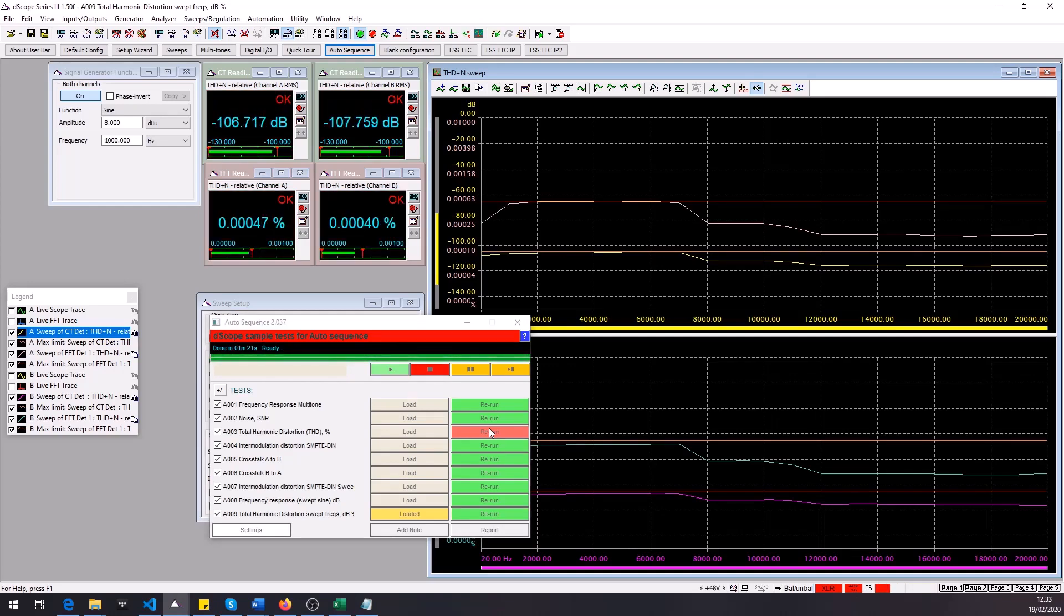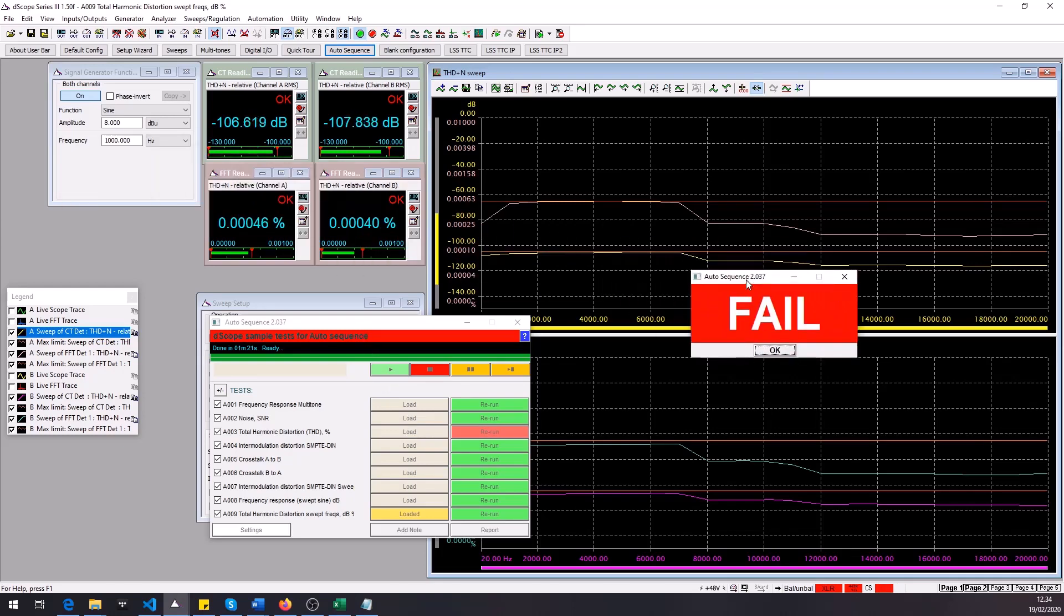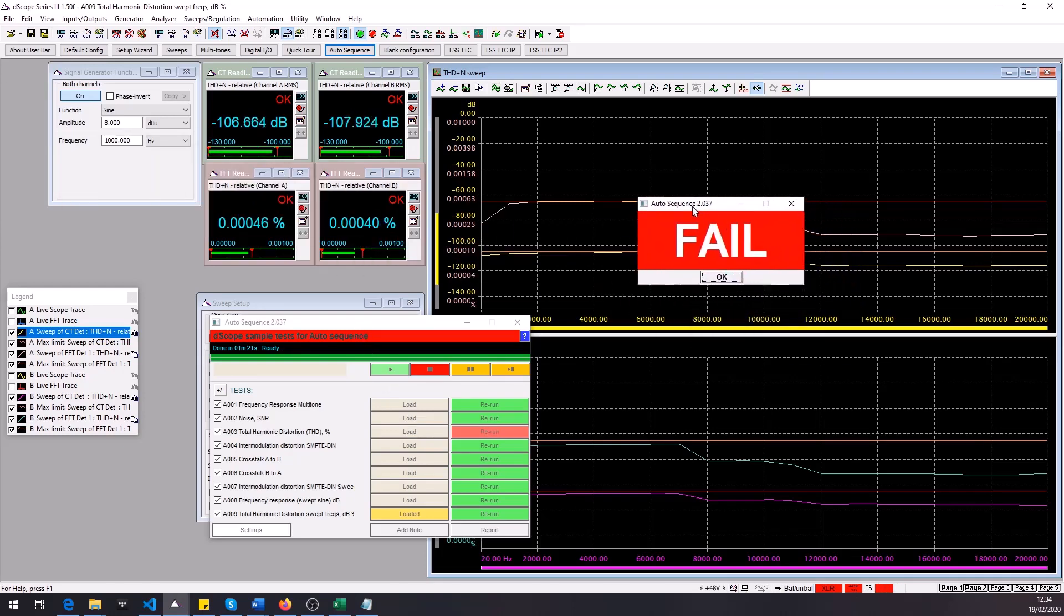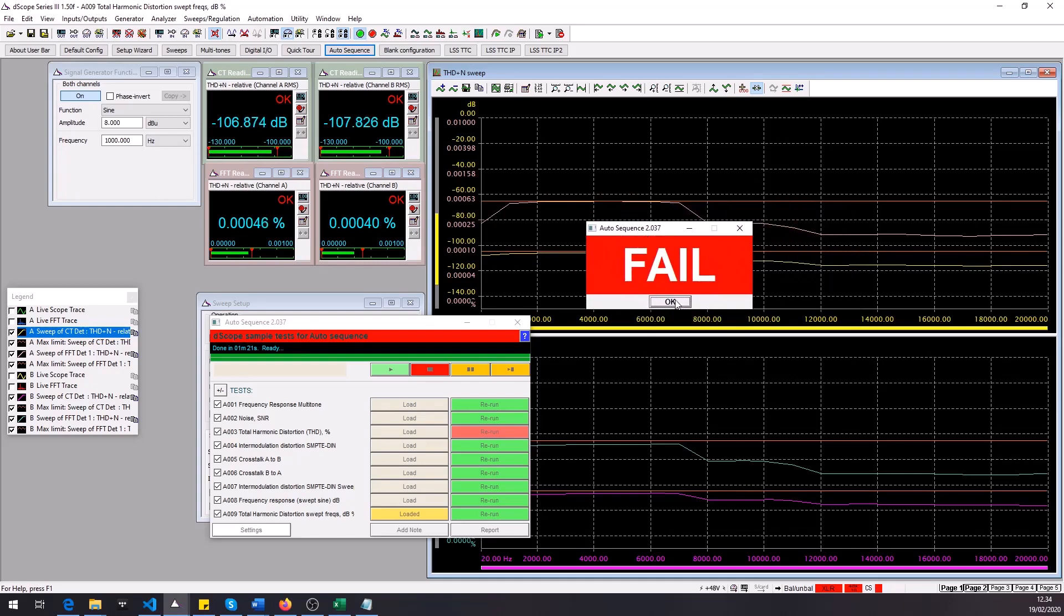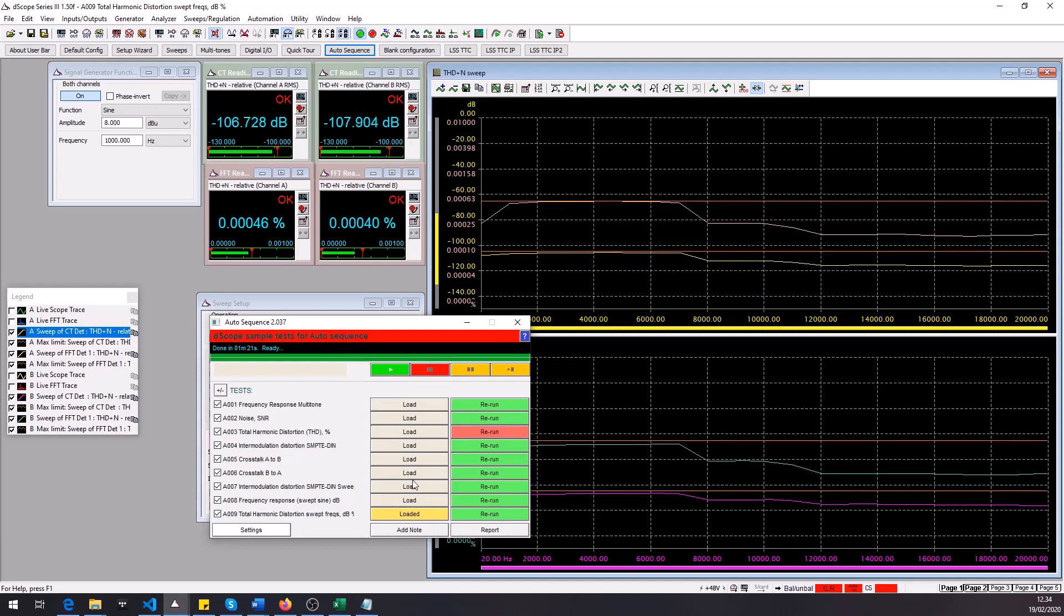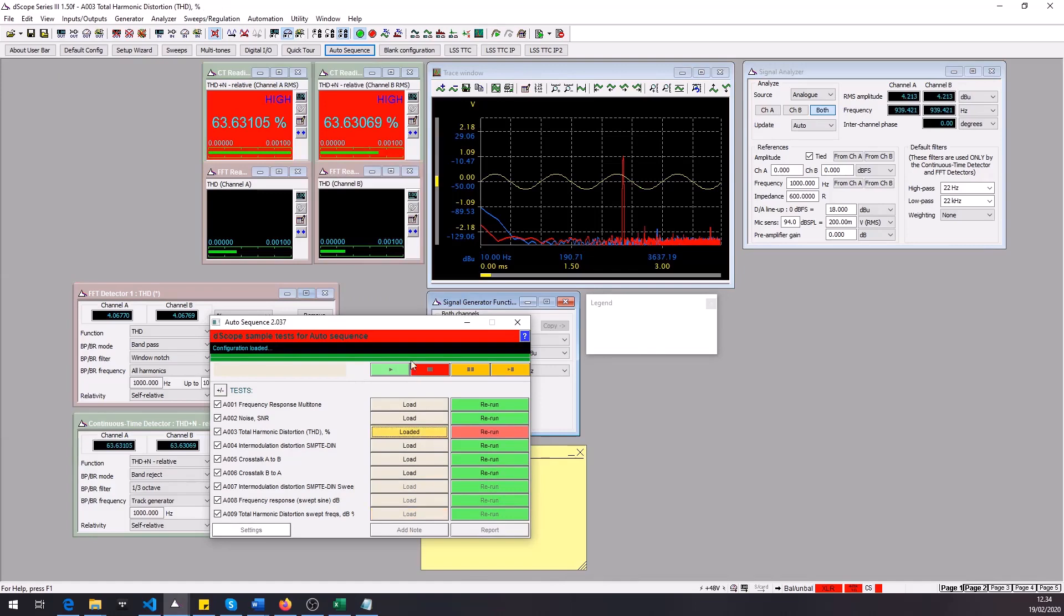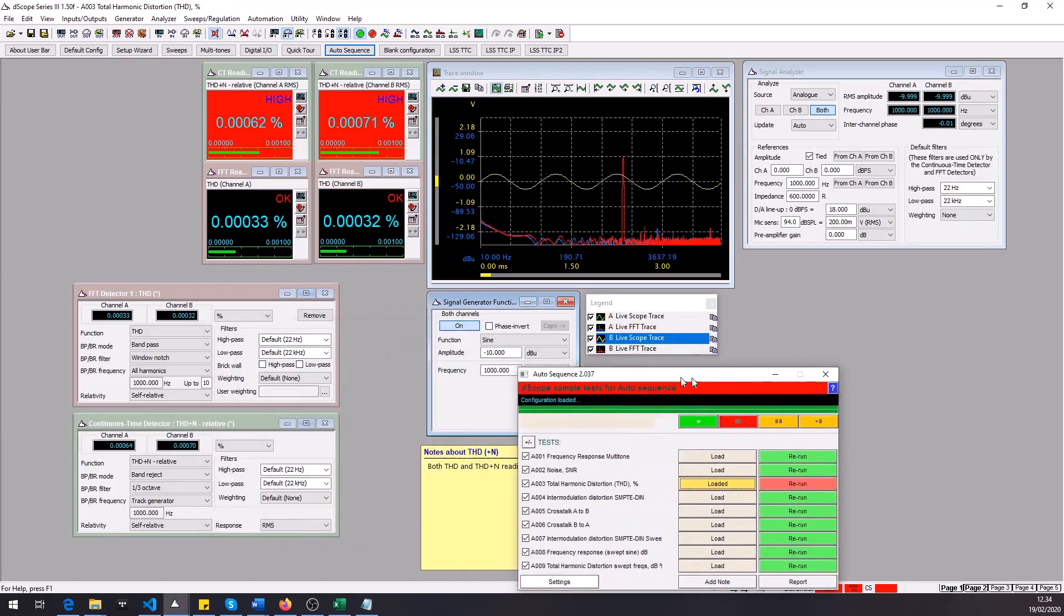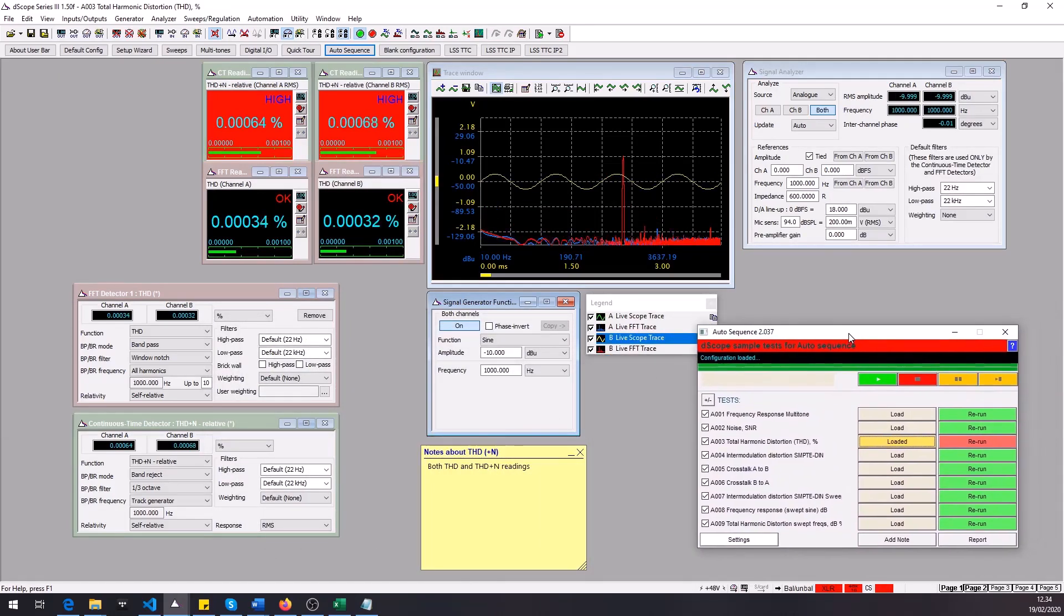All right it looks like all the tests except test number 3 passed so we're gonna load it. After you run the sequence you get this notification that it was a failure so we're gonna click OK and go back to test number 3 and let's take a look. It seems that THD plus N readings failed.